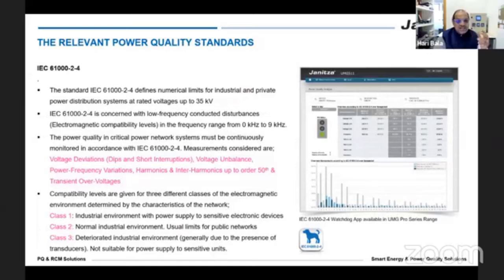Another standard, which is predominantly accepted towards the load: say, for example, a VFD manufacturer could say that I am complying to 61000-2-4. So this is coming towards the load, when they comply to a certain amount of current harmonics on the load side, not at the point of common coupling. If you're using multiple variable frequency drives, they may comply to 61000-2-4, but not essentially comply to EN 50160 or IEEE 519 at the point of common coupling, which is at the incoming of the main gate where we buy the power.